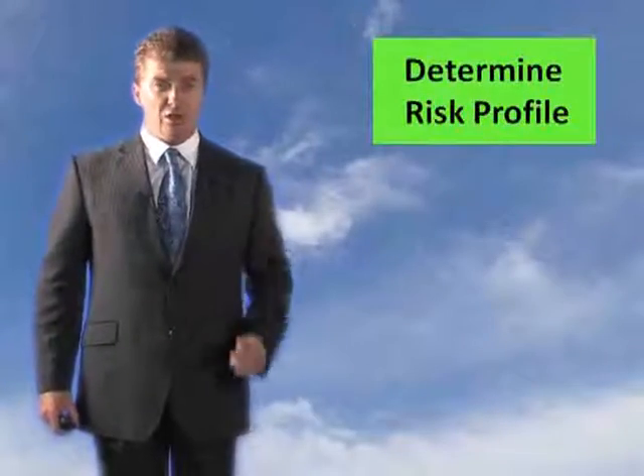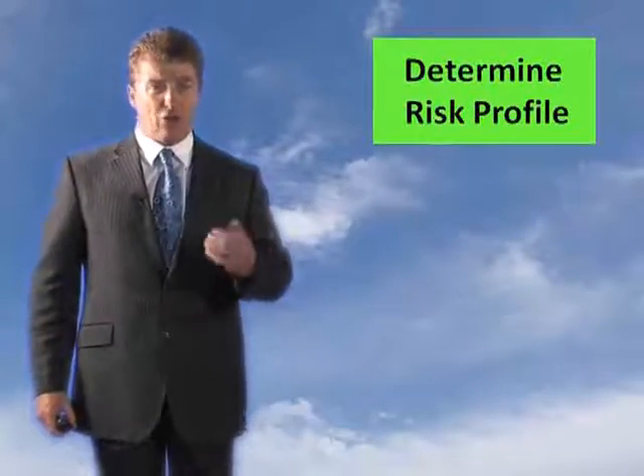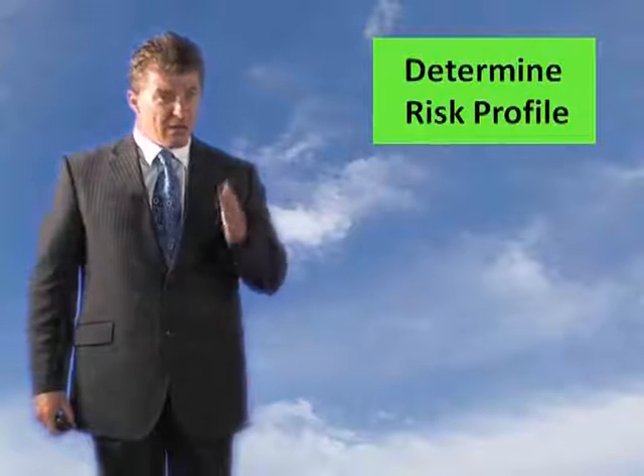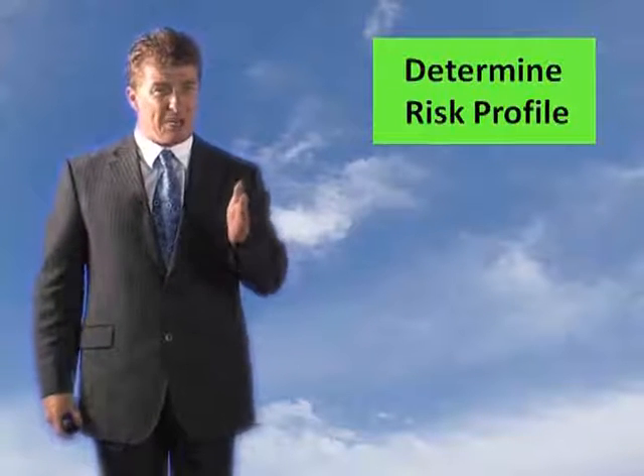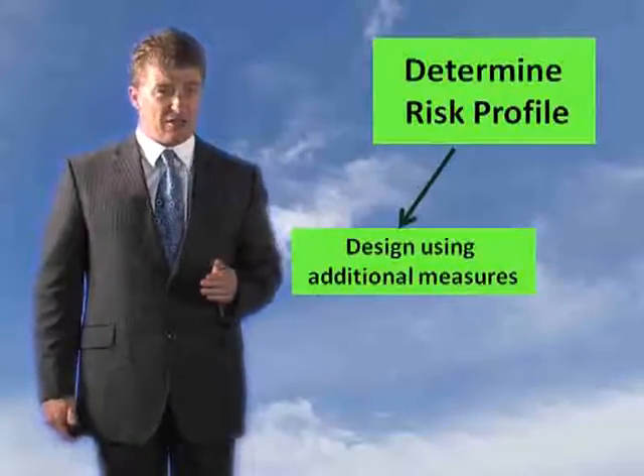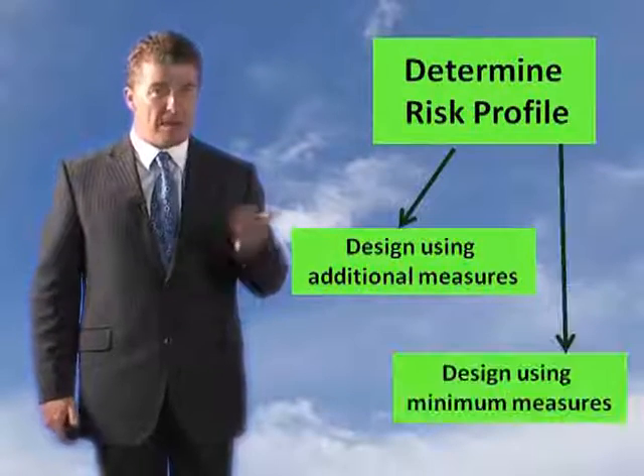Welcome to this section. How do you use BS 9999? Well, I'm going to go through the process with you now. The first thing you need to do is determine the risk profile. So you get that from the tables or you create it. If it's an A1 and A2, you need to get your risk profile. Then you can either use additional measures or you can design using the minimum measures.